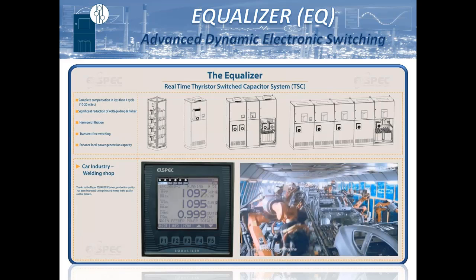Seeing as with a soft start in many applications, the only purpose is to minimize the impact on the network voltage of that motor start. With the equalizer system, it's accounting for that, so it can be utilized in place of that if necessary. And also with welding applications, there's the impact not only within the welding but also in neighboring production areas, so being able to isolate and mitigate the impacts in different areas.